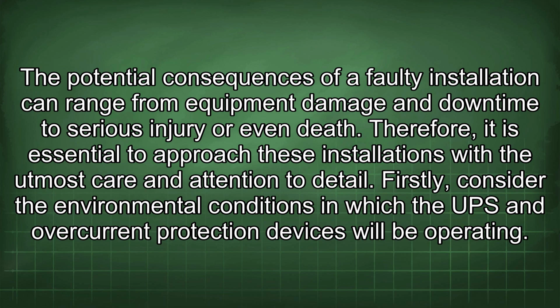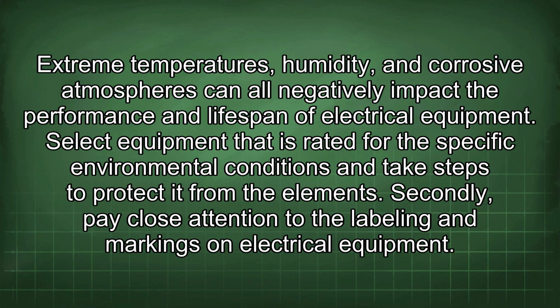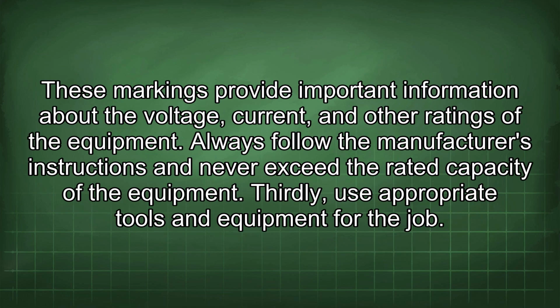Firstly, consider the environmental conditions in which the UPS and overcurrent protection devices will be operating. Extreme temperatures, humidity, and corrosive atmospheres can all negatively impact the performance and lifespan of electrical equipment. Select equipment that is rated for the specific environmental conditions and take steps to protect it from the elements. Secondly, pay close attention to the labeling and markings on electrical equipment. These markings provide important information about the voltage, current, and other ratings of the equipment. Always follow the manufacturer's instructions and never exceed the rated capacity of the equipment.